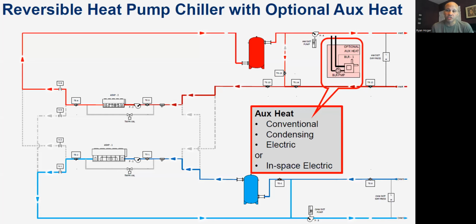If you don't want to get a chiller with a reversing valve inside it, or the machine that you need is so large that that's not really going to be practical, there are other things that you can in fact do. And this one is showing doing the reversing valves on the water side of the equation. So instead of having reversing valves inside the chiller, they're outside the chiller. And instead of the reversing valves reversing refrigerant, they're reversing water. So actually, that's the next one.